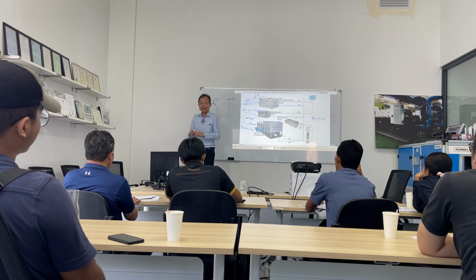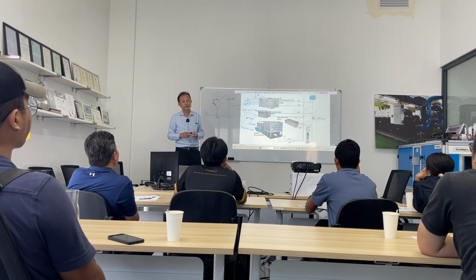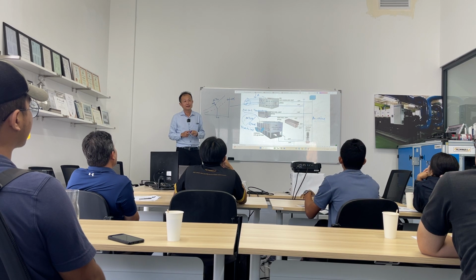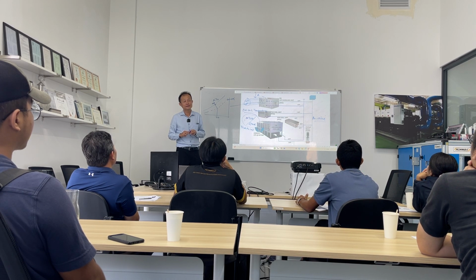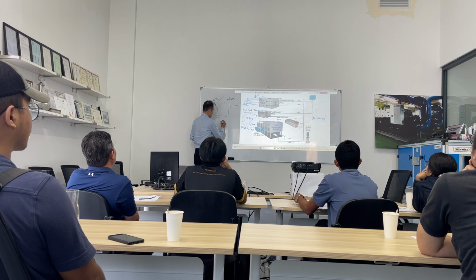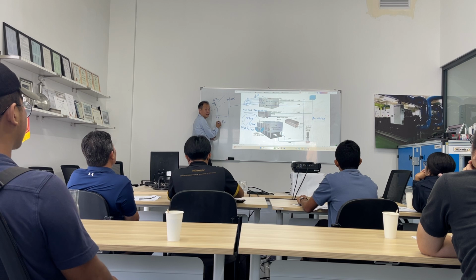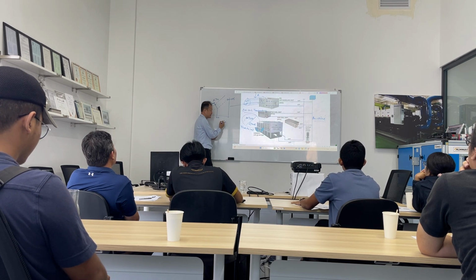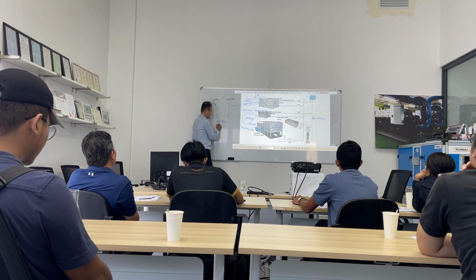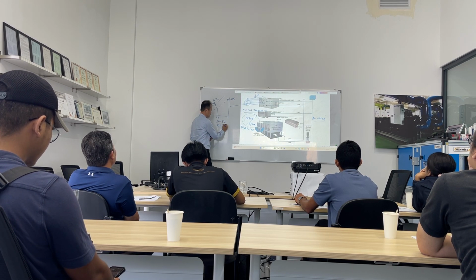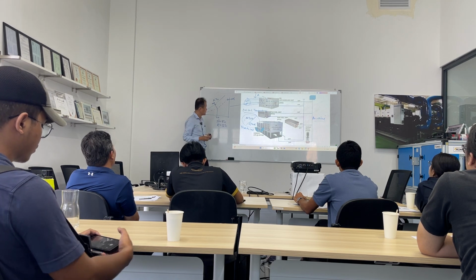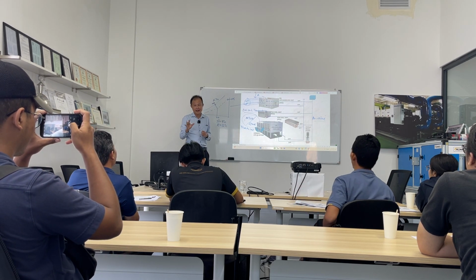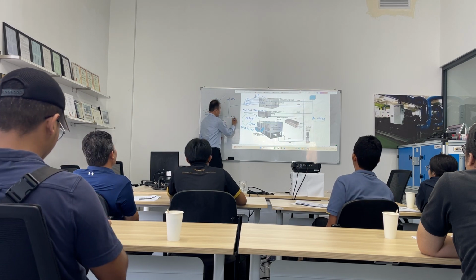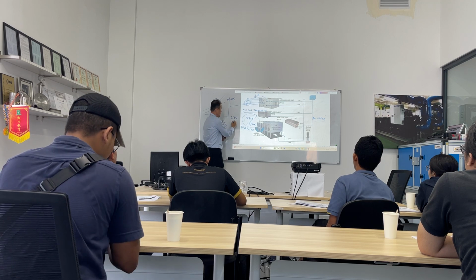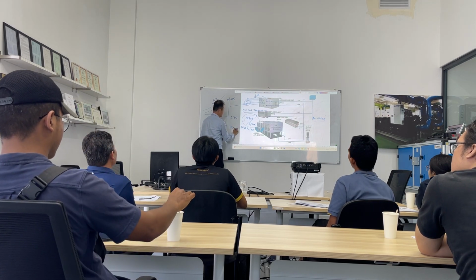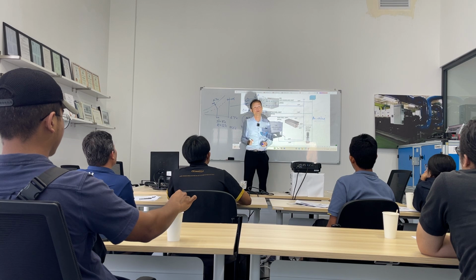So what is the standard temperature of chill water supply and return? Is it supply or return? Supply. And then return 12. Okay, under the ARI standard it is 6.7 degrees C supply chiller and return is 12.2, which is 44, 54.